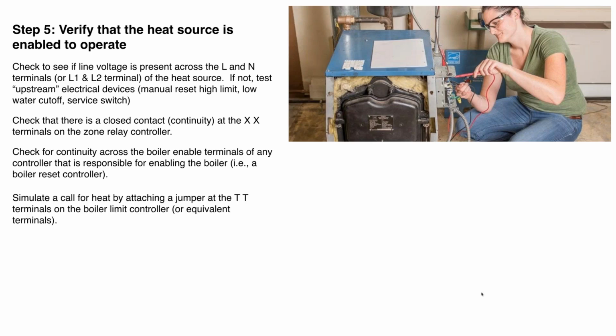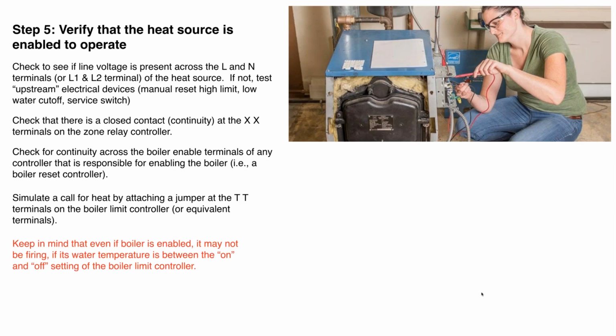And you can simulate a call for heat at the heat source. You can see here, this is an oil-fired boiler. It's got a pretty simple high limit control on it. Typically, you'll find a couple terminals marked with the letter T, and that was for thermostat. If you put a jumper between TT, you're in effect simulating a call for heat from whatever. It could be a thermostat, it could be some other controller in the system, but if you put that jumper across TT, you've verified you've got line voltage available, and you're not getting any response, again, it could be a problem with the high limit controller or something upstream of that, okay?